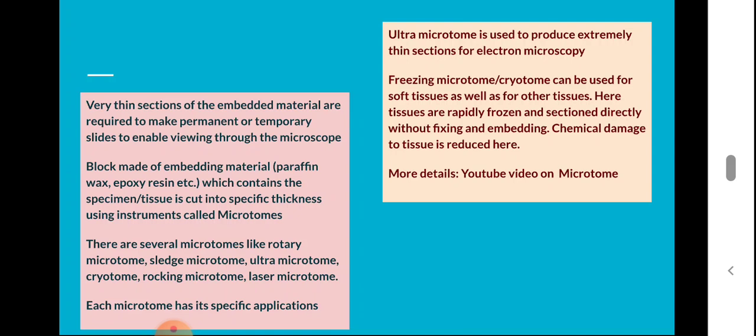The thickness of the section is very important while viewing the specimen through the microscope — the thinner the section, the greater the clarity, and we will be able to see the details of the tissues and cells. The block made of embedding material such as paraffin wax or epoxy resin is cut into a specific thickness using instruments called microtomes, where we can adjust and specify the thickness.